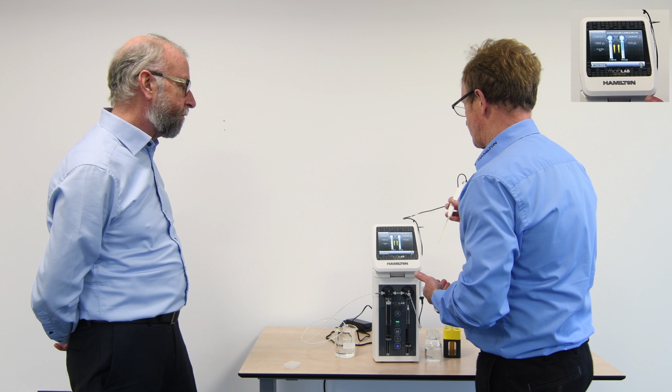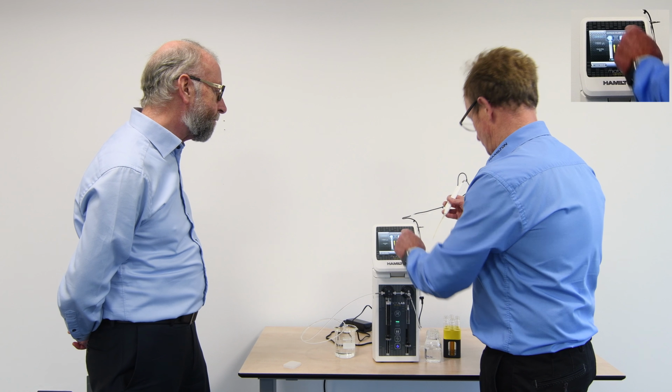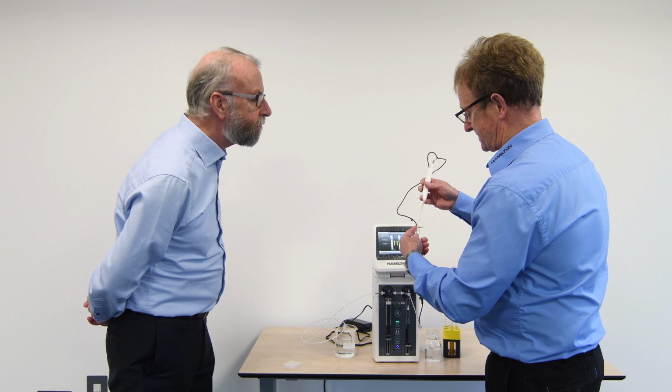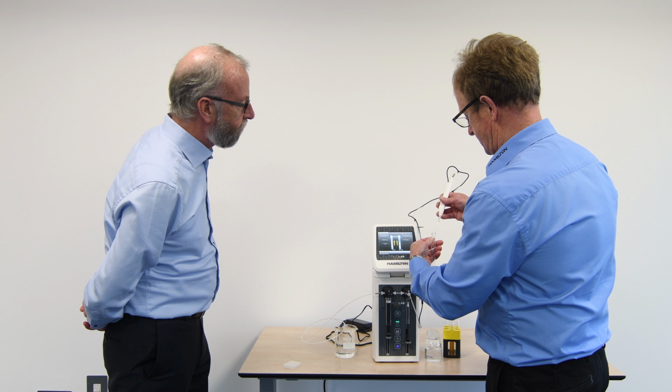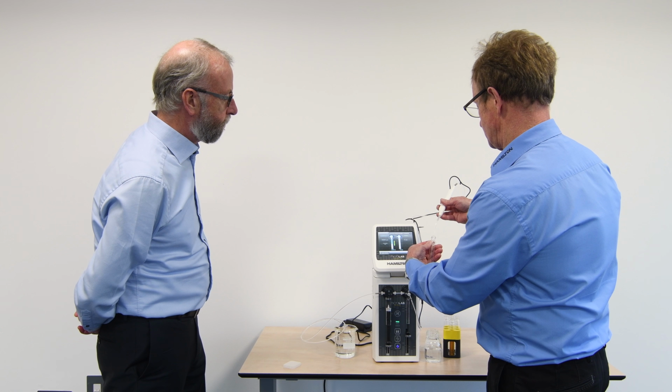Yeah. And now we've wiped our tip, and now we can dispense. It says dispense the diluent and the sample into the vial we're using. So we select our vial, add that into the unit, and you can see this sample, air gap and diluent came across.